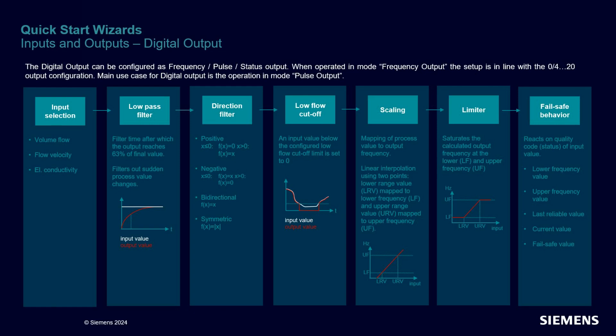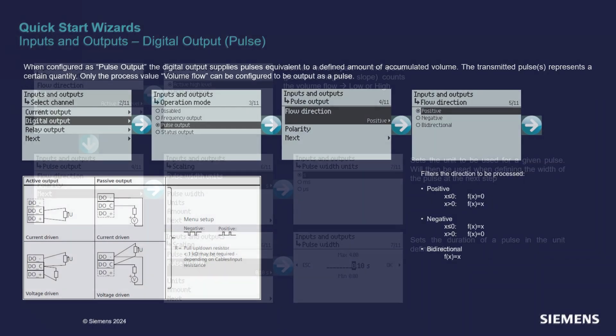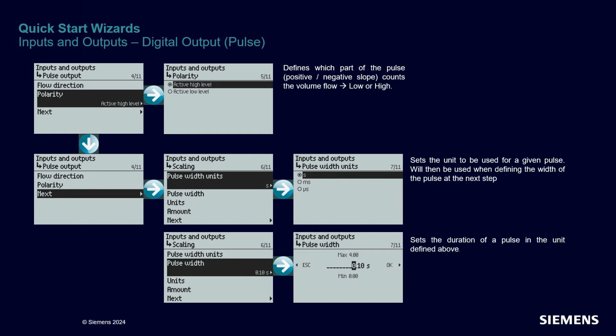We will skip over the details of the digital output as a frequency output so that we can focus more on the pulse output mode. When the digital output is set to pulse output mode, it supplies a number of pulses equivalent to an accumulated volume. The wizard starts by setting the desired direction of flow, then takes you through setting the desired polarity and the detailed controls of the pulses, such as the width.